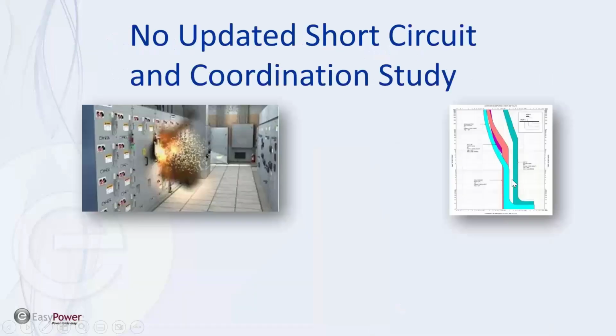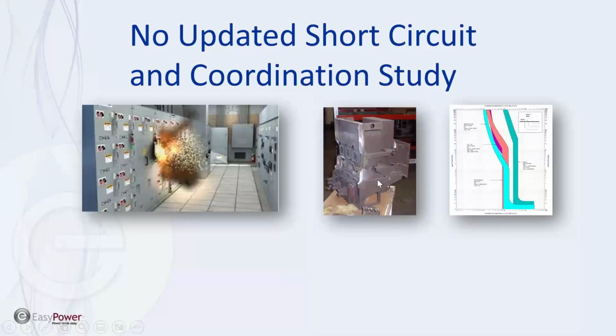Okay, so we talked about the coordination and short circuit study. So this is a breaker that was rated for 35,000 amps, 480 volt, 600 amp breaker. And so it's rated for 35,000 amps, and it was a 65,000 amp fault. So it didn't hold up, it blew up. Nobody got hurt in it.